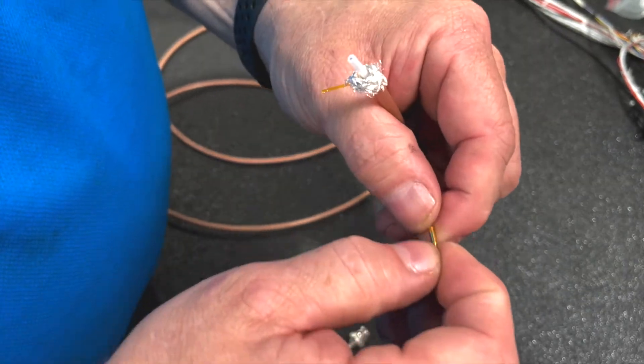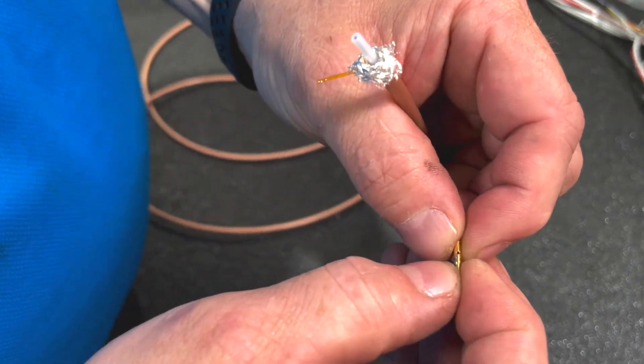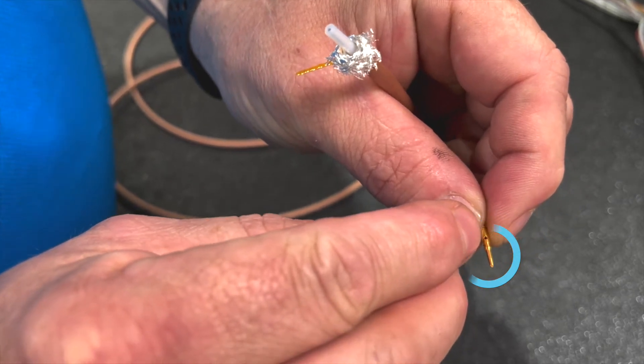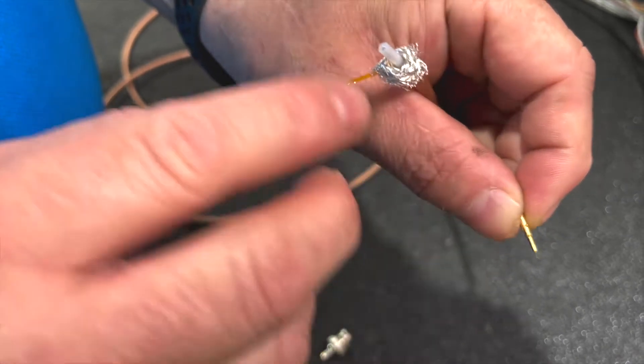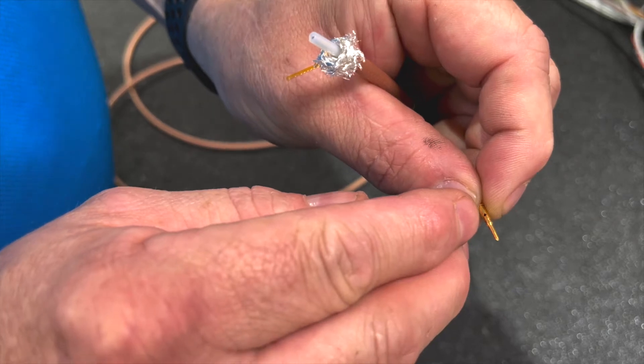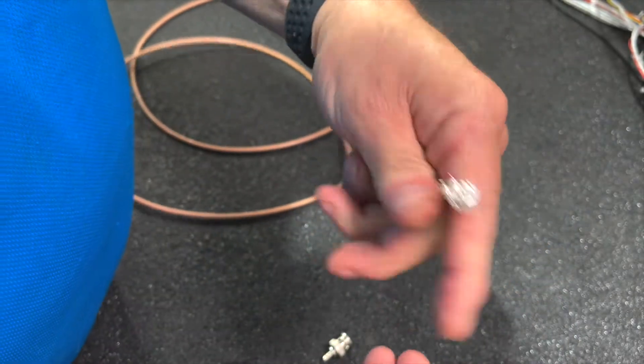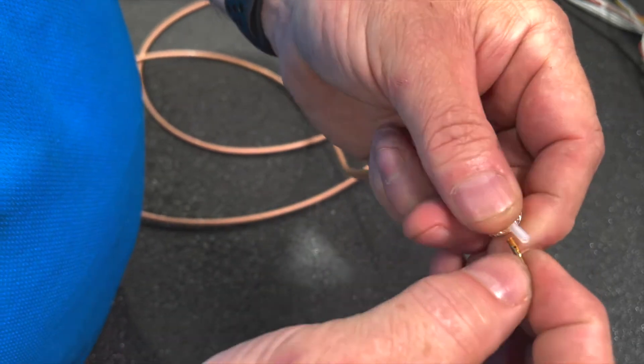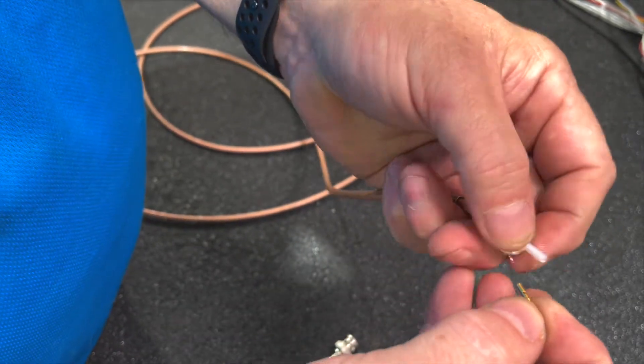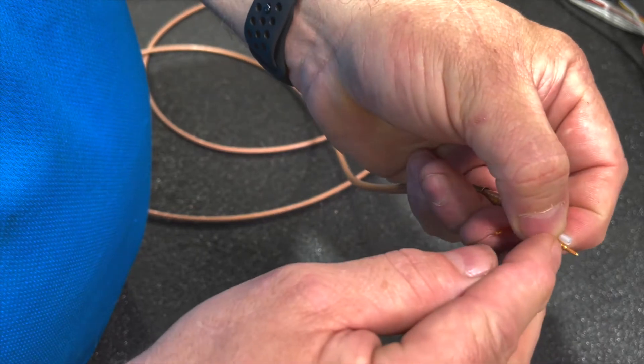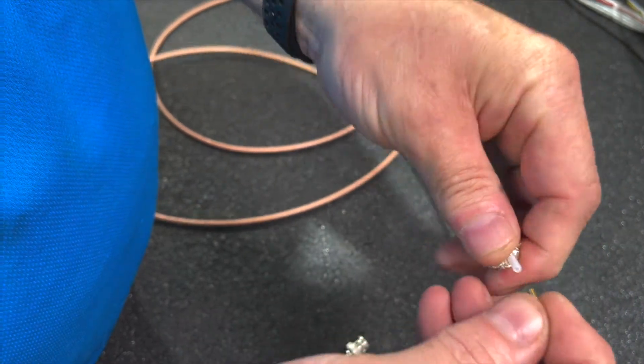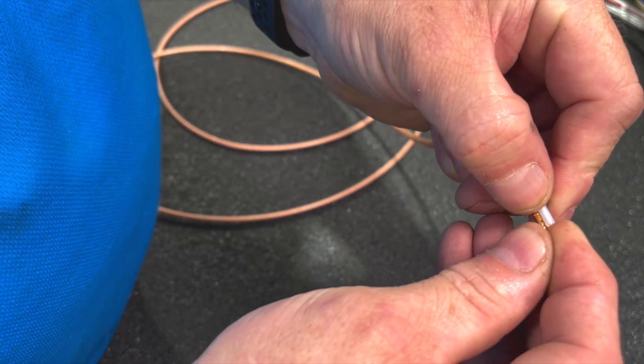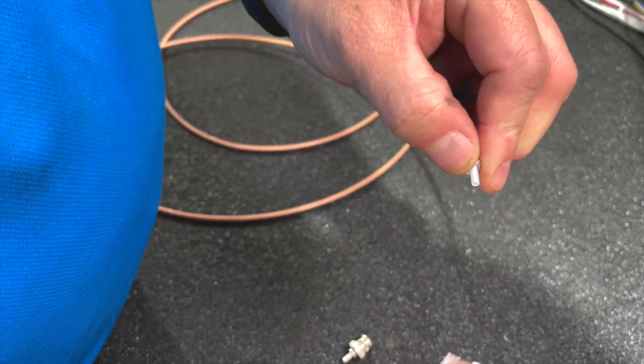Then we're going to take the pin itself, and if you look at the pin, there's just a tiny little window in there, a little round hole, and we should see the center conductor exposed through that little window. So what we're going to do is line this up until it's about at the top edge of that pin there, just above the window. There's a little shelf there. I'm going to line it up about to that and then I'm going to go ahead and score this.